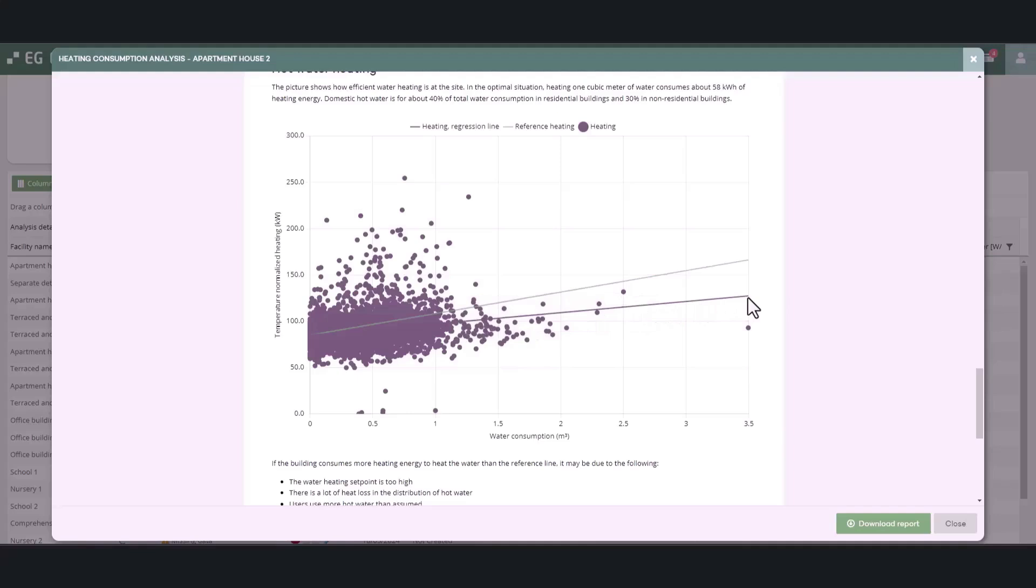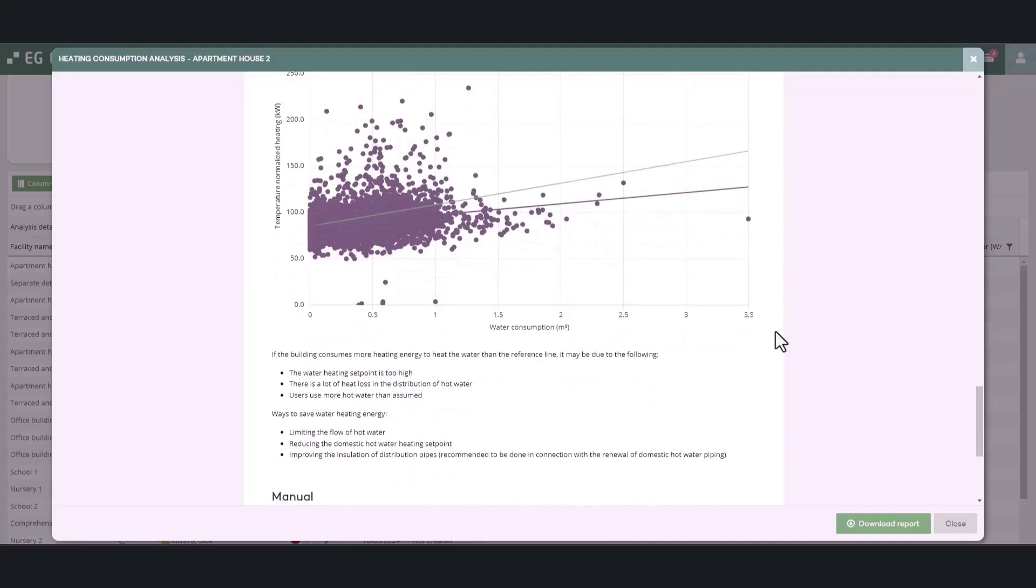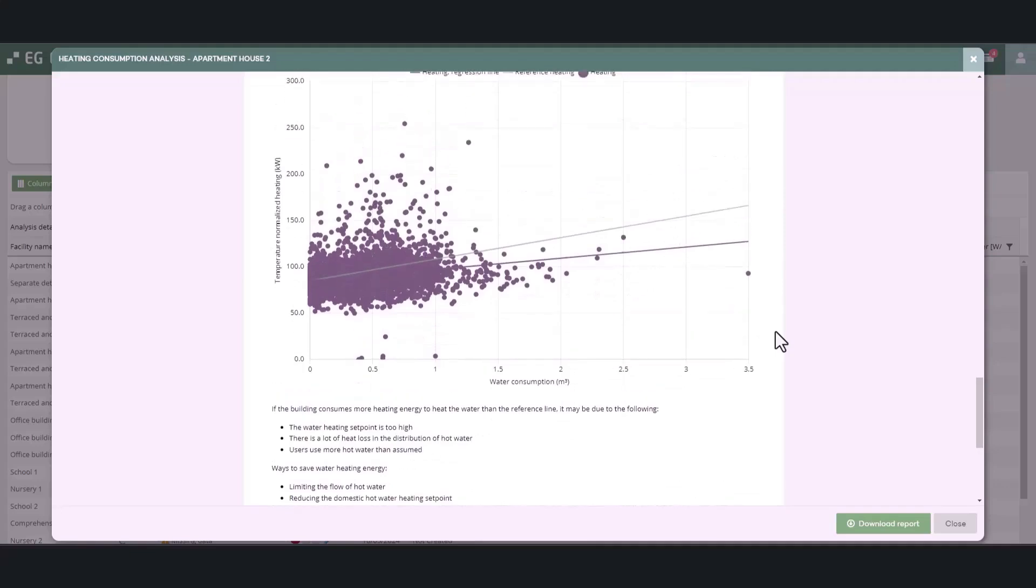If the regression line is higher than the reference line, it is recommended to check the domestic hot water heating settings. In this case, the regression line is lower than the reference line, which means that less energy is used to heat the hot water than in the reference facility.